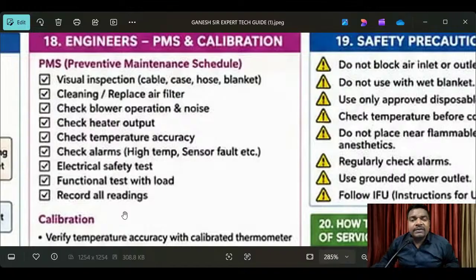By doing preventive maintenance, we can find out the issues, we can track the equipment, we can provide the services, and we can improve the services and reliability of our regular performance. Yes. Right, come on. Now, in preventive maintenance, I can see here: check blower operation and noise, check heater output, check temperature accuracy, check alarms such as high temperature, sensor fault, etc., and electrical safety test, and functional test with load, and record all readings. These are very important points before doing preventive maintenance as a biomedical engineer.